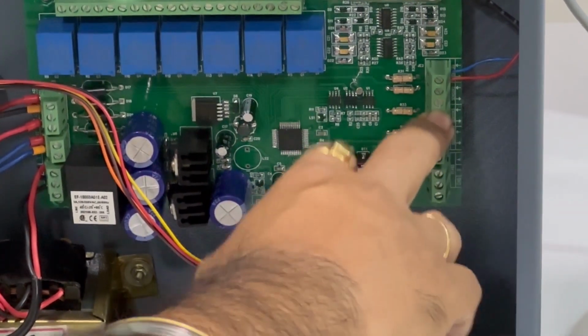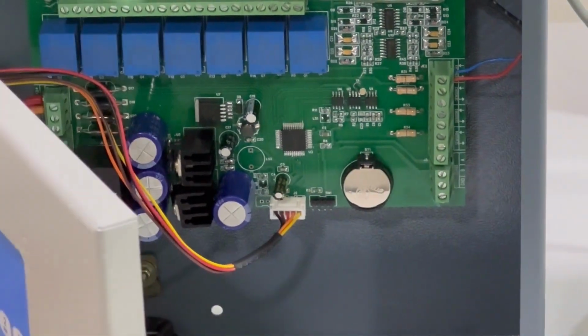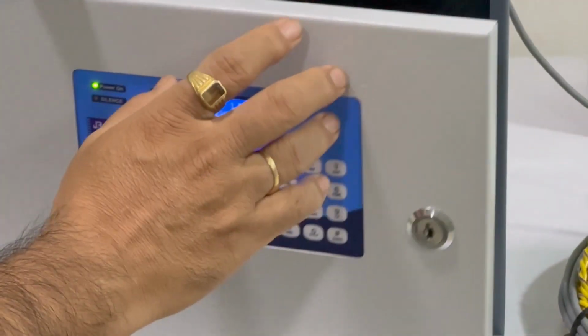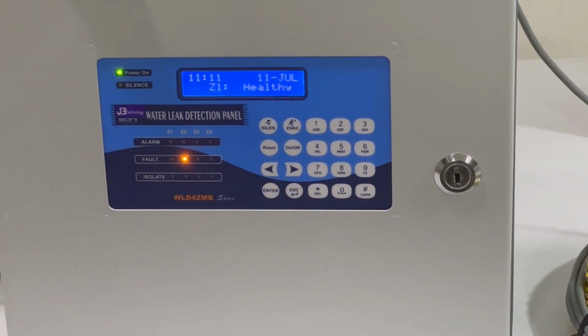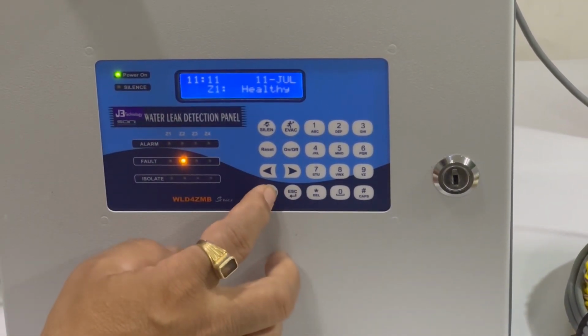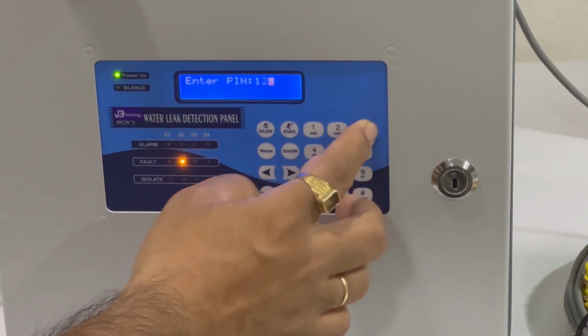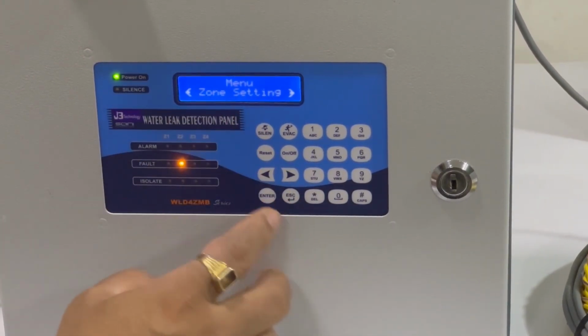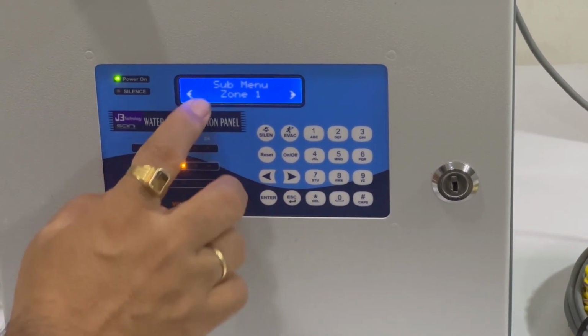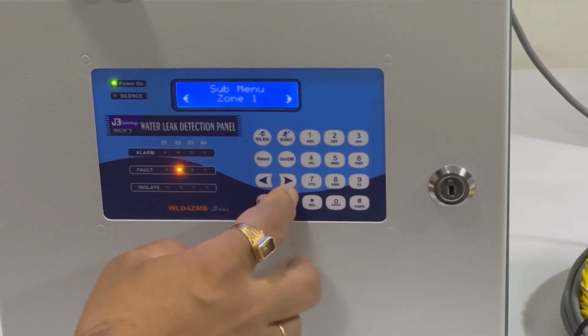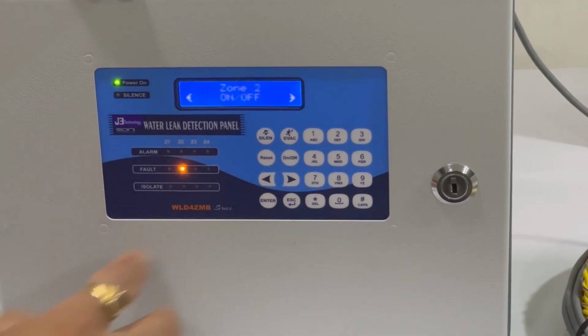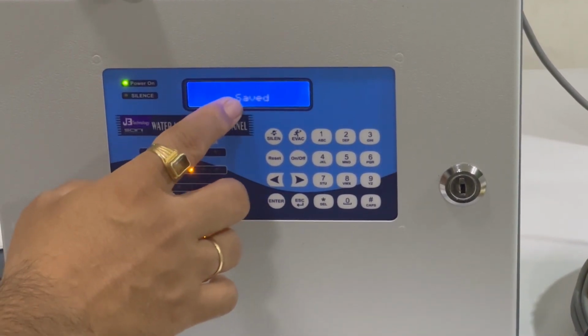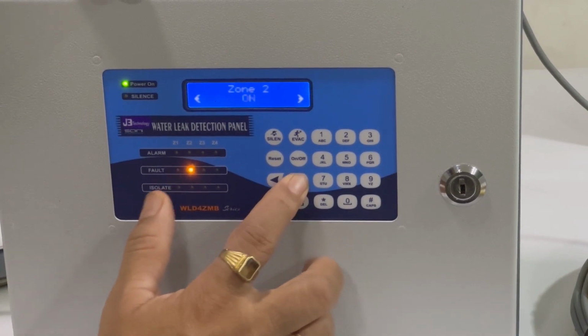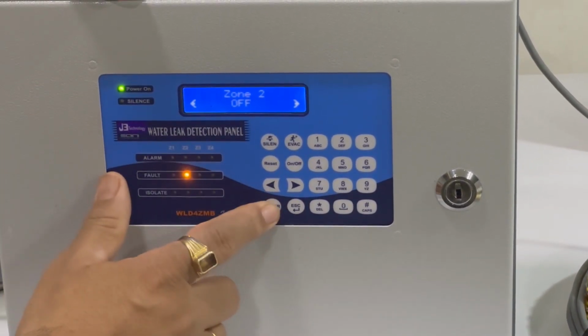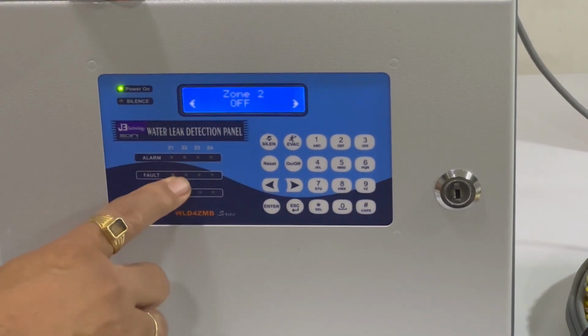So if you keep a zone on in the menu and you have not connected the cable, then the fault will always be showing. Suppose you are using only one zone, then this is the better option. Just go to the setting. Again you have to put the password. Zone setting, enter. Zone 1 is already working fine. Zone 2 is showing fault. Again zone 2, just push enter. Now you have to turn this zone 2 off. I have turned it off, and now I press enter. Okay, the fault indication has gone away.